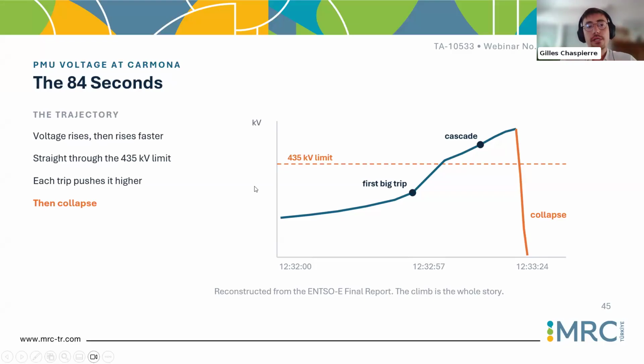So what is important is this 84-second voltage, as we discussed, is a very local variable, but also it varies very fast, while frequency can vary slower if you have, of course, sufficient inertia. What is important to highlight here is that already before the event, the voltage was high. And we will come back after that when I will explain in more detail. The voltage was high because the grid was slightly loaded. You had a lot of PV production.